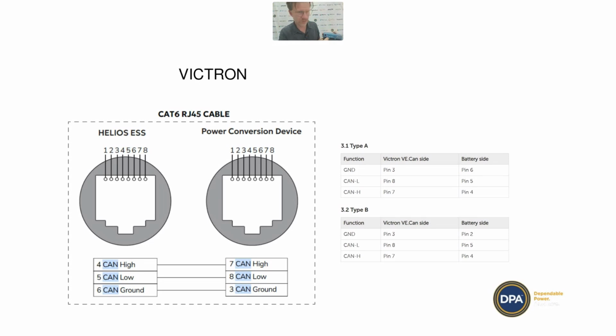Don't put it into the VE bus ports, and don't put an end terminator into the VE bus ports either. That's just for the inverter, and the end terminator causes problems because it's just for CAN bus. Also, don't put it into the Ethernet port here. It's an easy mistake to make, because if you do that, it will probably shut your inverter down.